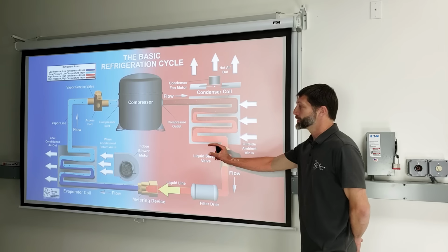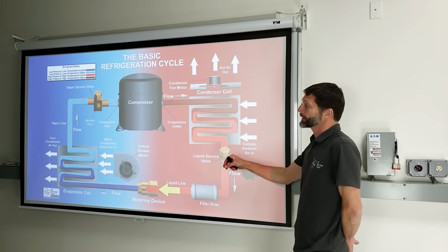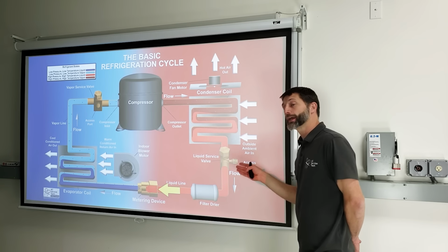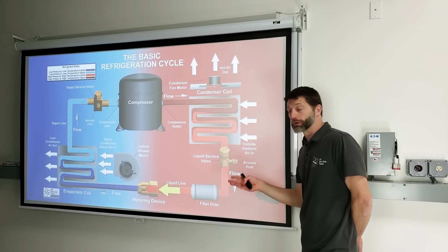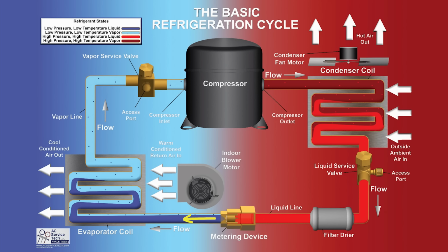And the phase change is the big secret to allowing the refrigerant to absorb heat energy from the air crossing the coil. And that is because anytime that the refrigerant is saturated, where liquid and vapor exist, it's always the same temperature as it travels through the coil until, in this case, it becomes fully vapor.